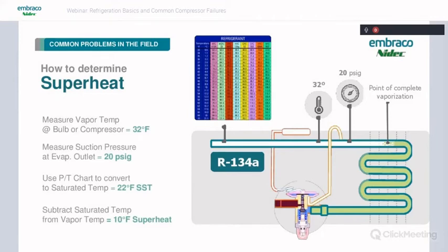Now that's measuring the suction line right out of the evaporator. If you're measuring the temperature of the suction line at the compressor, you're going to be looking for about 18 to 20 degrees of superheat. And that's going to guarantee that you're not getting any liquid refrigerant migration back to the compressor. So measuring out of the evaporator is where you're going to get those lower readings, and measuring at the compressor, you're going to be looking for 18 to 20 degrees. Now that's in an air conditioning application, so you may or may not be able to measure at the compressor in refrigeration. You may have more access to measure coming out of the evaporator. But basically what you're doing is measuring the temperature from the point of complete vaporization to this point right here on the suction line.